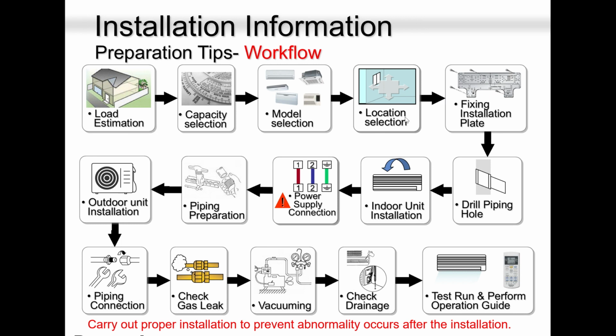Then comes the location. Don't just pick a location for your benefit. Pick the location for the customer's benefit. Make sure the unit is not blowing on someone's head or on someone's face. They will call you. They will call you 1 week, 2 weeks, 3 weeks down the road. They got chills. They got colds. They got stiff necks. Because the unit is blowing straight on their face. So all you have to remember is the location. Very important. Above windows is not a good idea. Above doors is not a good idea. Facing the people sleeping on the bed or in a living room, directly on them, it's not a good idea. It's not a good location.